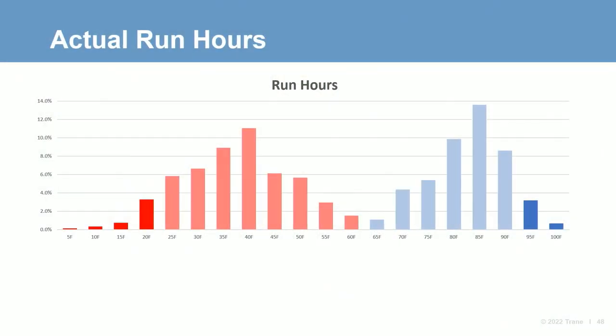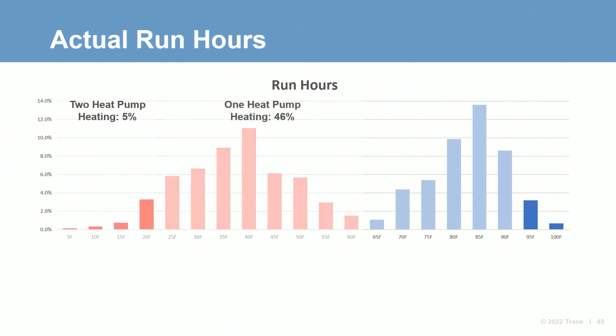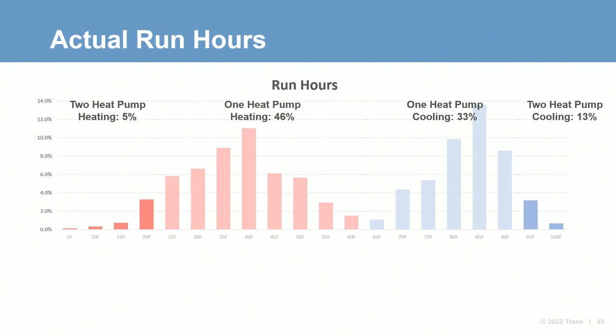This chart is showing you percent of total run hours in ambient buckets throughout the year. The first bucket is showing you the coldest ambient conditions for the year and requires two heat pumps in heating mode. This bucket only has 5% of the total operating hours and shows you just how little peak heating is happening throughout the year. The next bucket is one heat pump in heating mode and comes in with the highest weighting of 46% of the run hours. One heat pump in cooling contributes a third of the run hours, and two heat pumps in cooling mode has 13% of the run hours.